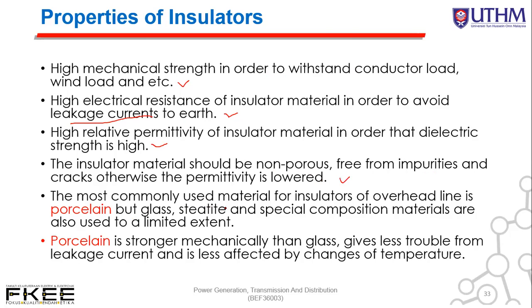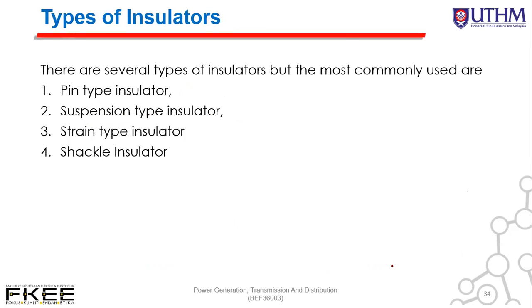And the most commonly used material for insulator of overhead line is porcelain glass. Okay, porcelain but glass. Porcelain with glass. Steatite and special composition material are also used to a limited extent. Why porcelain? Because porcelain is stronger mechanically than glass. Okay, give less trouble from leakage current and is less affected by changes of the temperature. Okay, now we see the types of insulator, there are 4 types of insulator. That is pin type insulator, suspension type insulator, strain type insulator, and also shackle insulator.